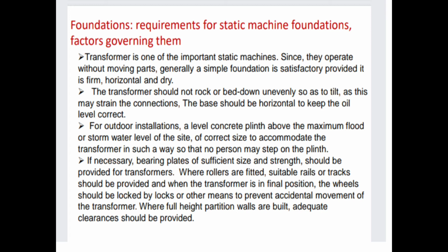The third point is, for outdoor installations, a level concrete plinth above the maximum flood or storm water level of the site, of correct size to accommodate the transformer in such a way that no person may step on the plinth. The fourth point is, if necessary, bearing plates of sufficient size and strength should be provided for transformers. Where rollers are fitted, suitable rails or tracks should be provided, and when the transformer is in final position, the wheels should be locked by locks or other means to prevent accidental movement of the transformer.